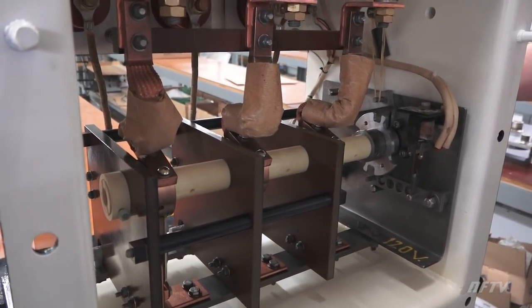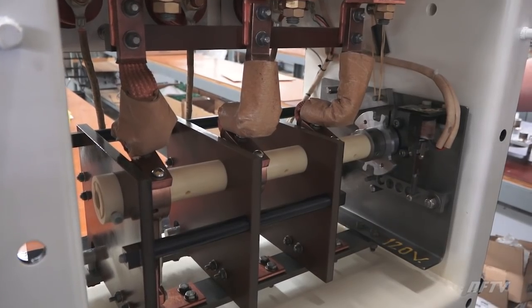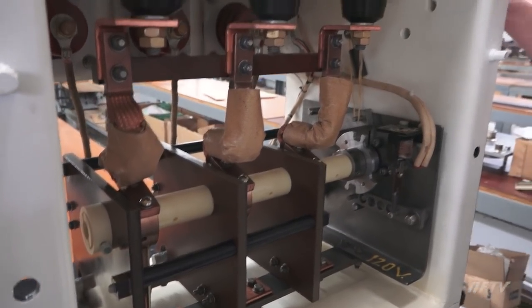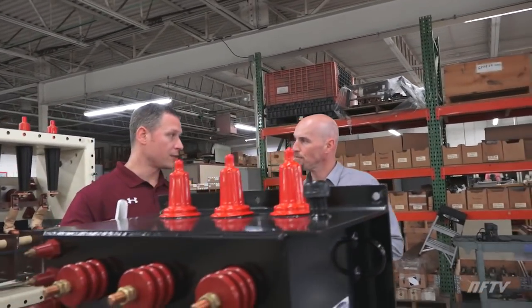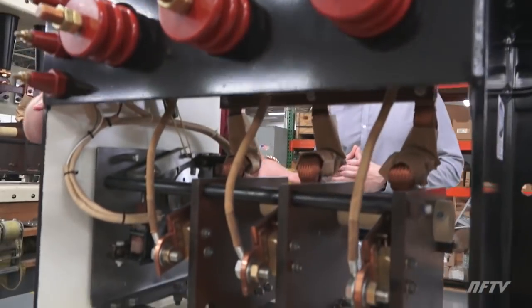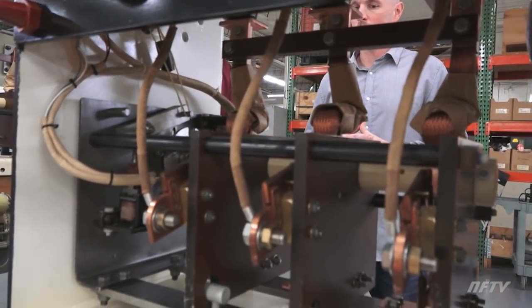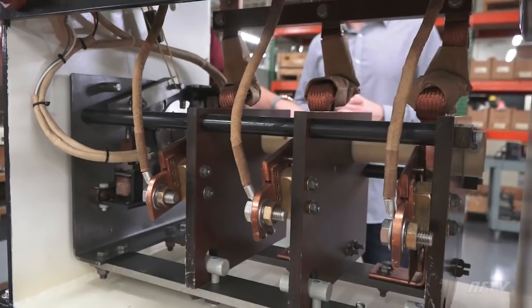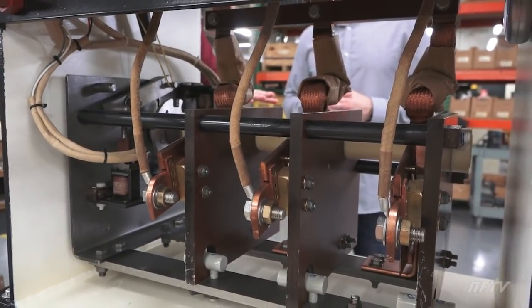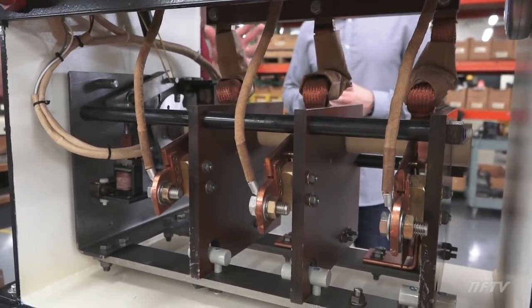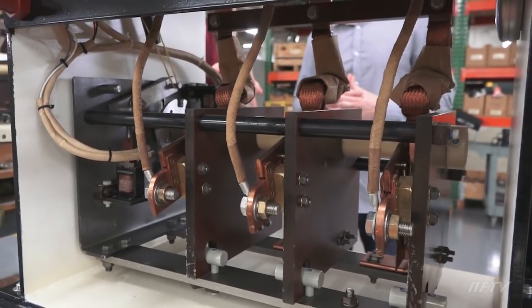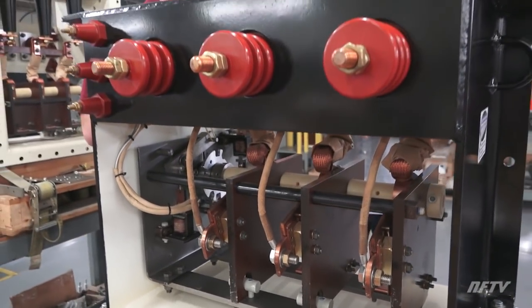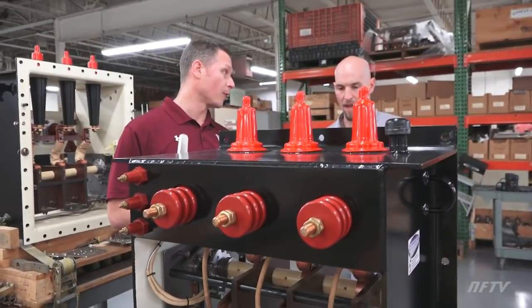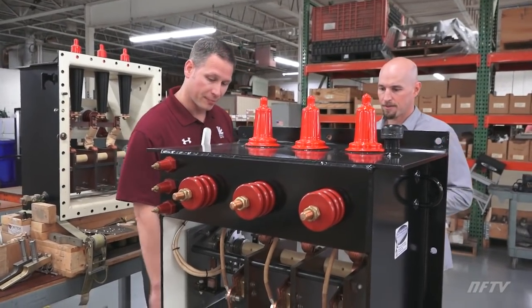What would the purpose of this be? What would this be used for particularly? So if a utility line worker is underground in one of these vaults working on one of these transformers or a section of the network that this transformer is hooked up into, they would want to ground out that device to make sure it's safe to enter that vault. They ground this device so they're ensured there's no issue, in case somebody re-energizes it and turns it on when they're not supposed to, it holds together and there's no arc or explosion in the vault while they're down there working. Excellent, awesome, good to know.